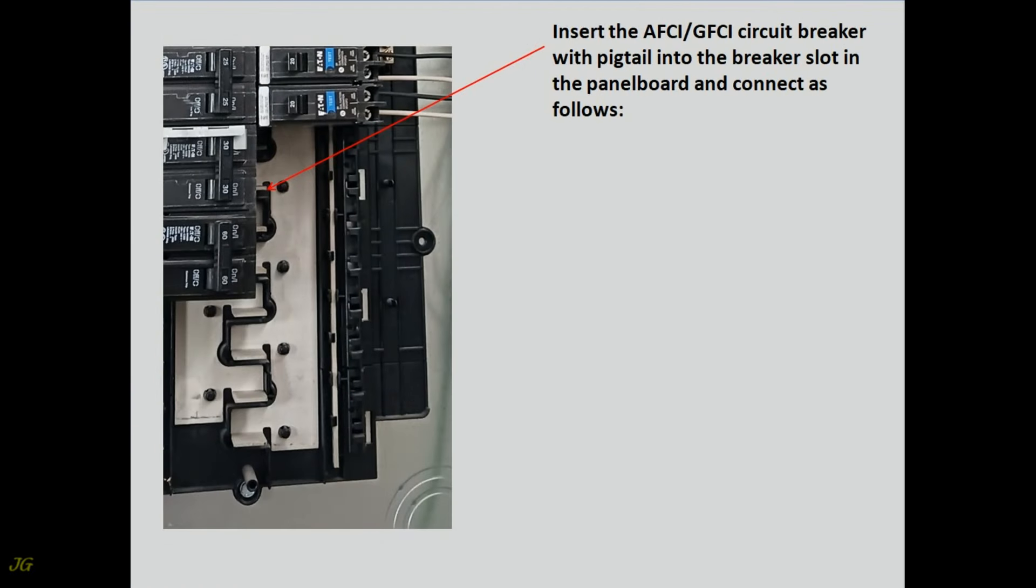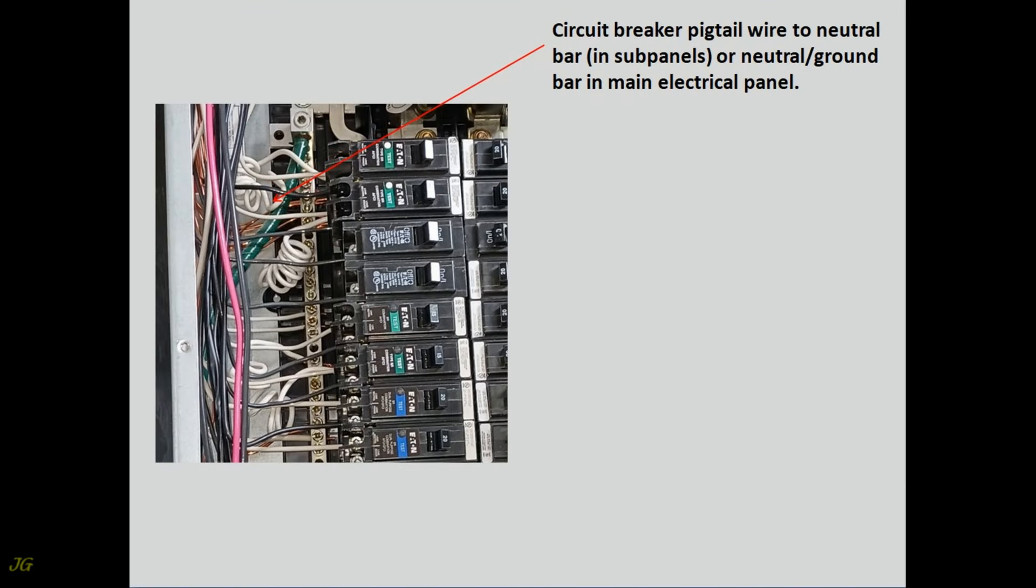Insert the AFCI GFCI circuit breaker with pigtail into the breaker slot in the panel board and connect as follows: circuit breaker pigtail wire to neutral bar in subpanels, or neutral ground bar in main electrical panel.